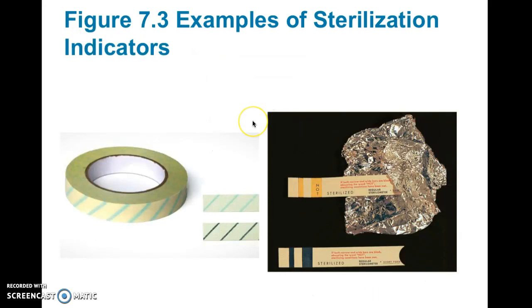And how do you know that autoclave has worked? You put stuff in, you seal a door, you turn it on, you come back an hour or so later. Every time you run one you have to include a sterilization indicator. One example is a roll of tape. It has pale blue or pale yellow stripes. When it starts, if the autoclave has gotten to a high enough temperature and pressure, they turn black.